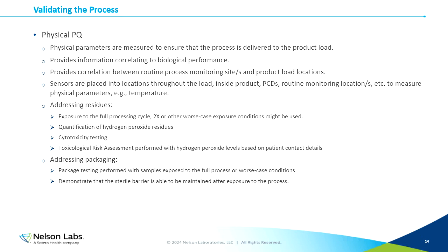Once we get those numbers, we can also perform cytotoxicity testing. We may have samples that are devoted to that test specifically. So that's something we may perform. But what we do once we get those hydrogen peroxide residue numbers, a toxicological risk assessment is performed with the residue numbers, and we base that on patient contact details to determine whether the product has safe levels of residues or not.